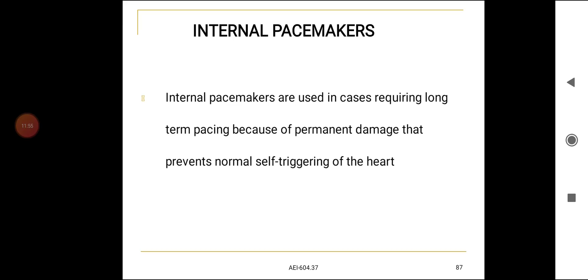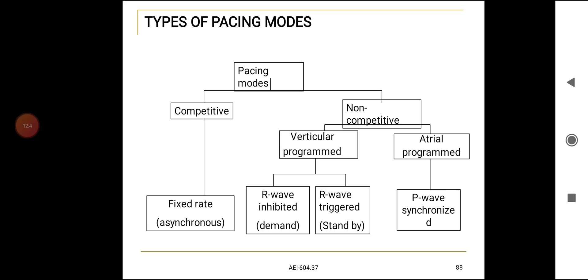Types of pacing modes. One is competitive, another is non-competitive. The competitive one generates a fixed rate of pulses, that is, asynchronous. Non-competitive is classified into two: ventricular programmed and atrial programmed. Atrial programmed is used for P-wave synchronized pacing. Ventricular programmed can be classified into two: demand pacemaker and standby. Demand pacemaker is R-wave inhibited, whereas standby is R-wave triggered.